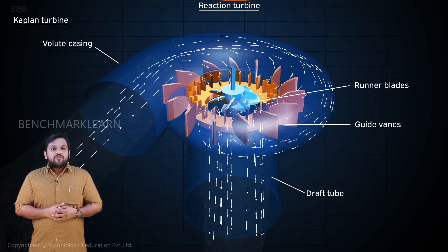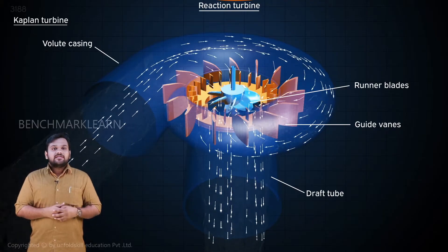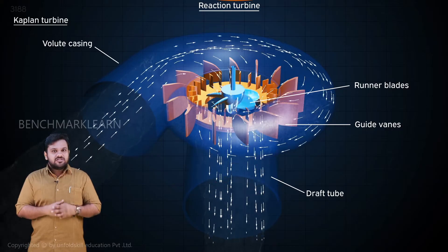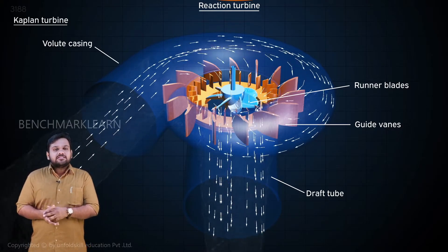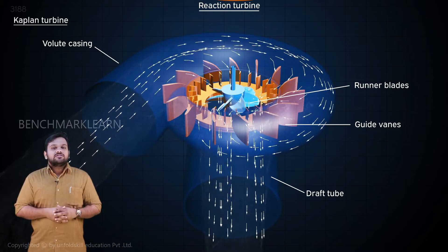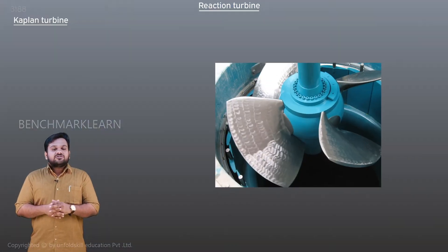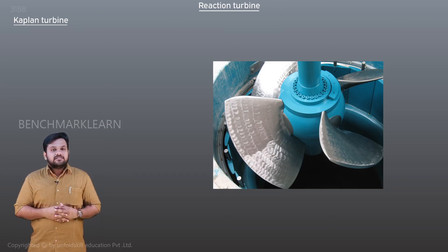Kaplan turbines are usually used as low-head turbines, typically below 40 meters. They are used to extract the last bit of energy from water. Besides this, they are also used in ships for propulsion. The Kallada project in Kerala uses two Kaplan turbines of 7.5 megawatt each at a rated head of 45 meters.